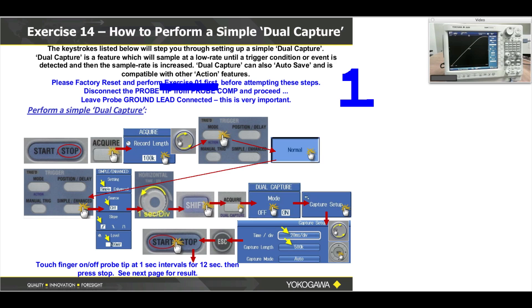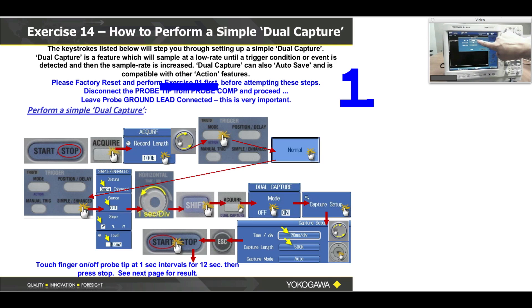With your finger on the shift button, press shift then press dual capture — it's a sub-function of the acquire button, right here under start/stop. Soft menu button number one is mode on — that turns on dual capture. You now have a main window at the top and the dual capture window at the bottom. Soft menu button number two is capture setup. Press it, and for the time per division adjust that to 20 milliseconds per division using the big knob.